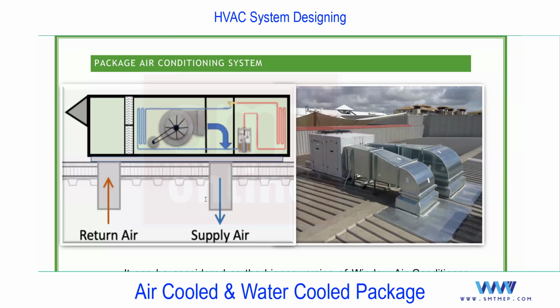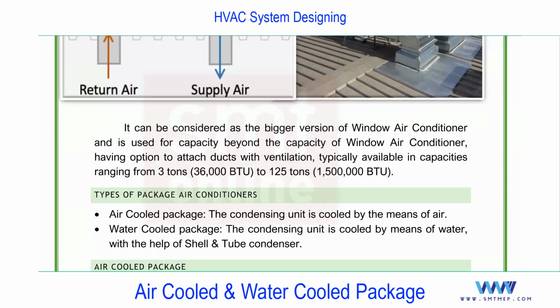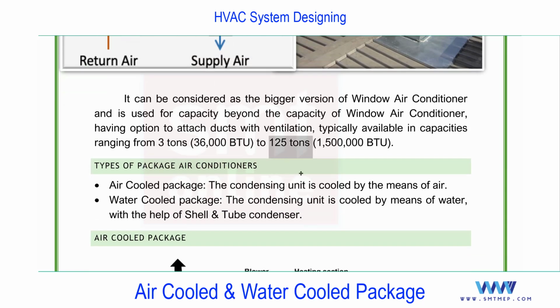You see what I explained? It can be considered as a bigger version of a window, with capacity beyond that of a window, and we can attach the duct with the ventilation. Typically it is available starting from 3 TR up to 125 TR, and in the market you'll find 360 or 400 TR, more than that, depending on the make and model. In general, from an entry point of view, you can use this option.